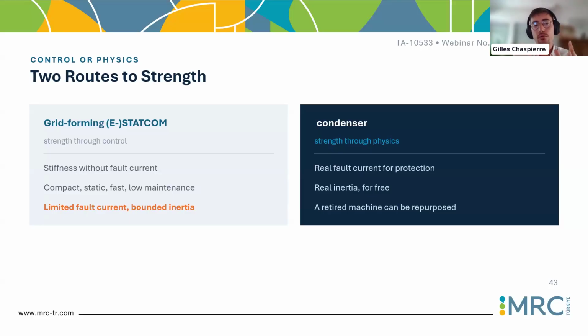So basically, there is no better candidate. They are complementary, and it depends on your local system needs. If you need a large amount of inertia and if you need a high short circuit current to make sure the protection works properly, better go for a condenser. If you have a limited footprint, but at the end you just need fast voltage control, voltage source behavior in the vicinity of some grid following assets, go with grid forming STATCOM. They are a bit complementary, and again, detailed dynamic studies are needed to decide which technology is better than the other for the specific system needs.